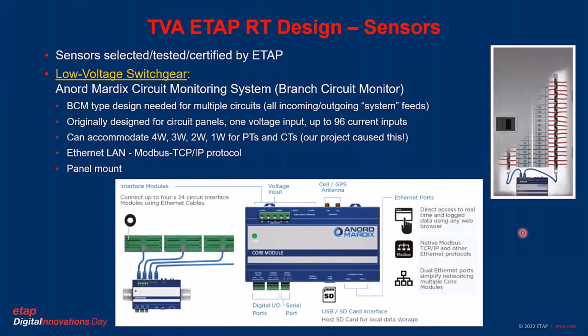For our low voltage switchgear, the sensors that were selected, tested, and certified by ETAP were Anord Mardix circuit monitoring system sensors, which are also known as a branch circuit monitor. I've got a little picture over here of what you may more typically think of as a branch circuit monitor, used in a power panel or a breaker box. And I thought this was a very unique and smart application on ETAP's part to suggest this, because what we have in our case on our 480 volt switchgear is one voltage measurement for the bus, but many currents in and out. And that's exactly what this branch circuit monitor is designed for.